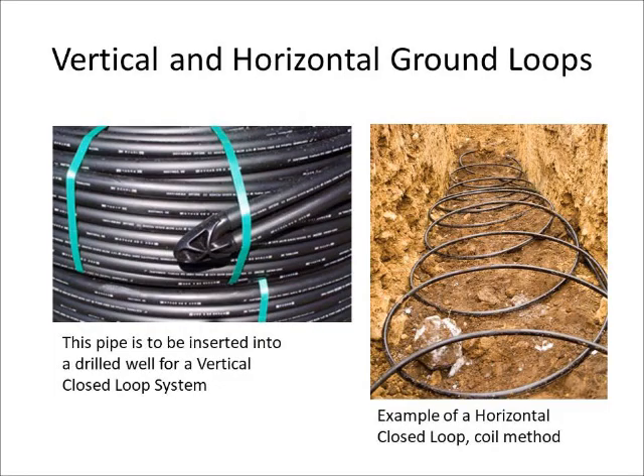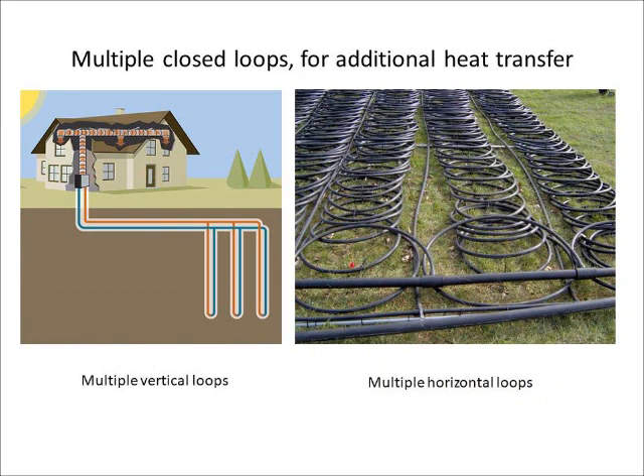These photos are examples of vertical and horizontal ground loops for a closed system. The photo on the left shows two pipes joined together, which would be inserted down the vertical shaft of a drilled well. And the photo on the right is the coils of a horizontal loop system laid out underneath the frost line in the ground. Multiple closed loops can be used for additional heat transfer, either vertically or horizontally.